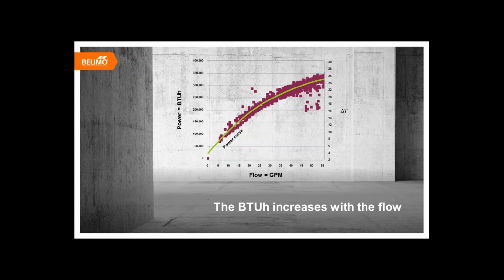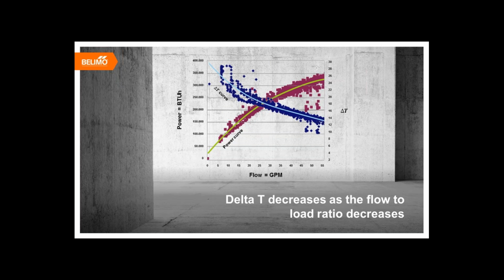Let's take a look at it actually on a graph. This is some actual data points from an air handler we have at MIT. The power output, as you can see in the graph, increases across the green line as the flow increases. When we add the delta T data points to the graph, we can see that the delta T decreases as the flow increases.